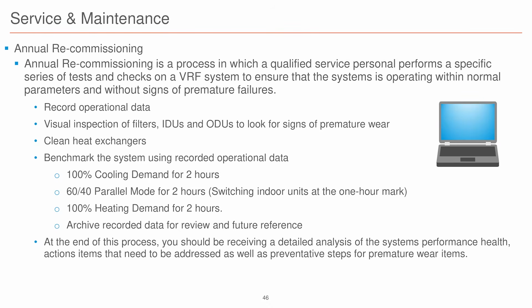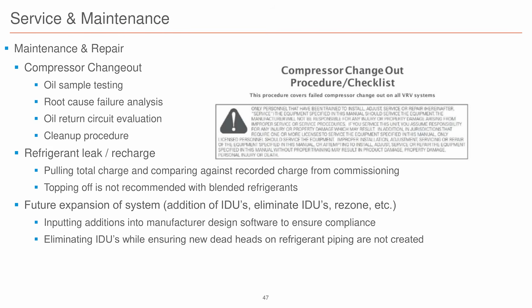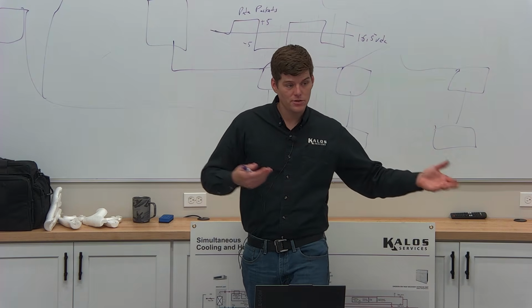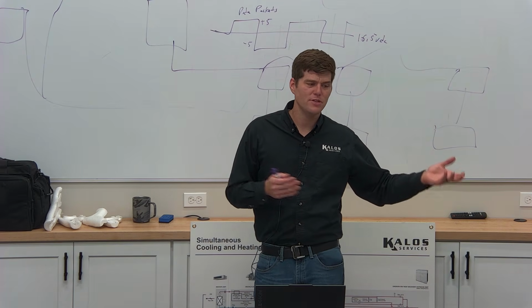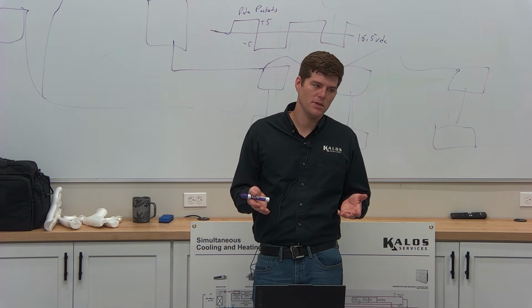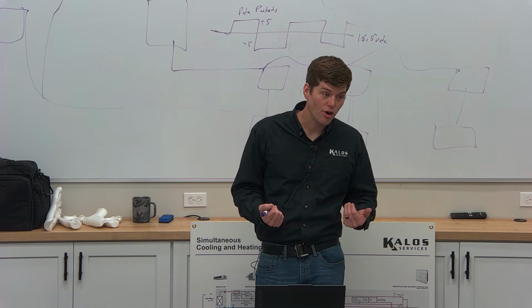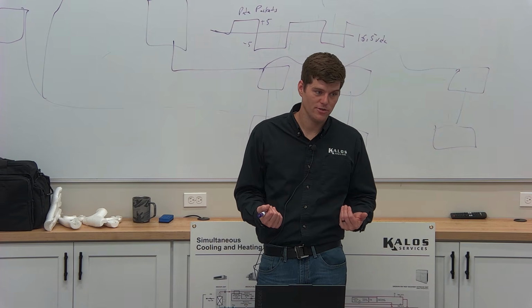Service and maintenance, oil samples, and so on. We'll get into all this stuff when we do service classes. Refrigerant leaks, recharges. We don't typically like to top off a VRF system, right? When we measure liquid line sets on a system, it's a specific charge. There's no way to gauge the amount of refrigerant in a system. Sure, there are ways and methods to do it, but there's really no way to be certain, especially if you've never touched the system or installed it in the first place. Pull the entire charge, weigh the entire charge, and then recharge based upon that.